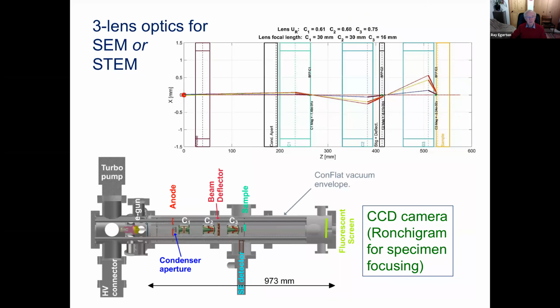Here is a ray diagram for a 3-lens optics, as you might need for a scanning electron microscope or a STEM machine, with 3 lenses between the electron source and the specimen. And on the bottom, cross-sectional diagram of the column. So on the left-hand side, we have our connection to the high voltage. We have the electron gun, a turbo pump to provide the vacuum, and electrons are accelerated towards the anode plate, which is at ground potential.